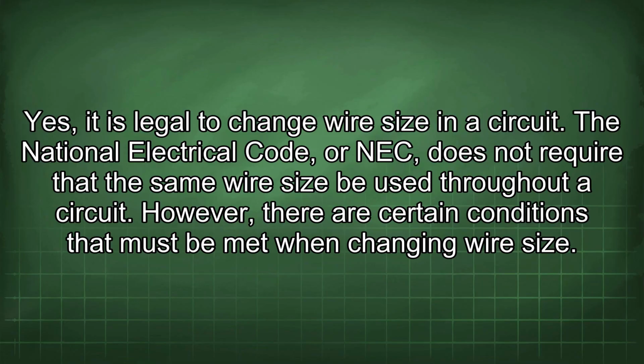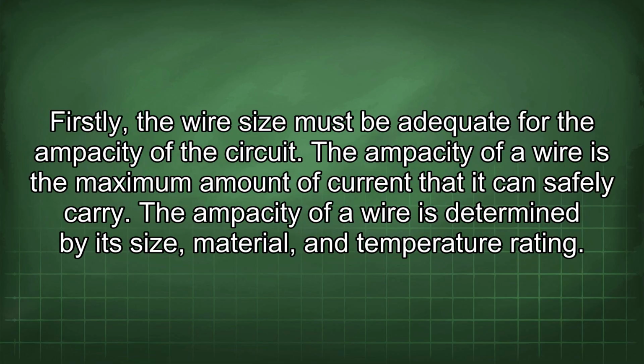Yes, it is legal to change wire size in a circuit. The National Electrical Code, or NEC, does not require that the same wire size be used throughout a circuit. However, there are certain conditions that must be met when changing wire size. Firstly, the wire size must be adequate for the ampacity of the circuit. The ampacity of a wire is the maximum amount of current that it can safely carry. The ampacity of a wire is determined by its size, material, and temperature rating.